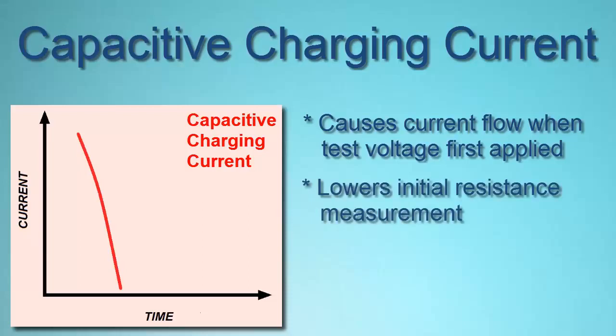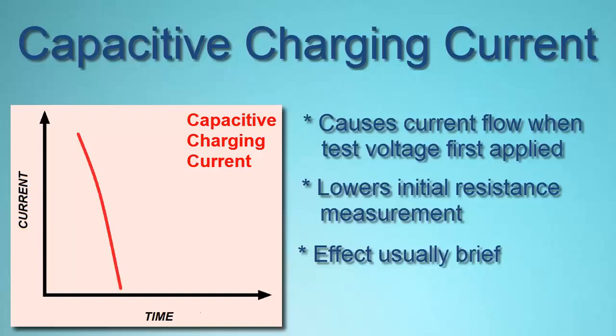This effect is usually brief, often lasting less than a second, although in very long cables or large motors, this can last much longer, up to 30 minutes or more. Capacitive charging current is not an indicator of insulation quality, but it needs to be accounted for to assure your measurement is meaningful and relevant.